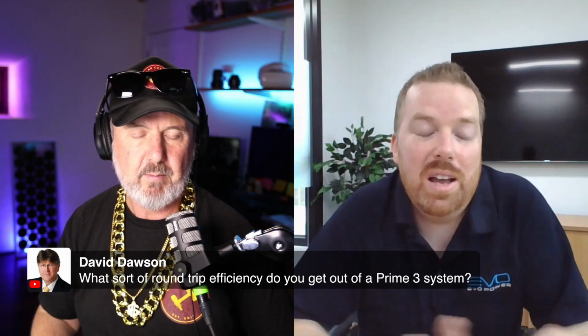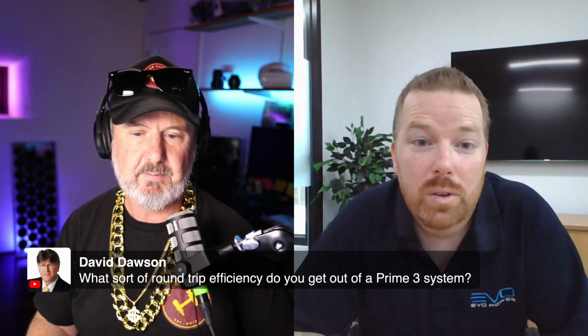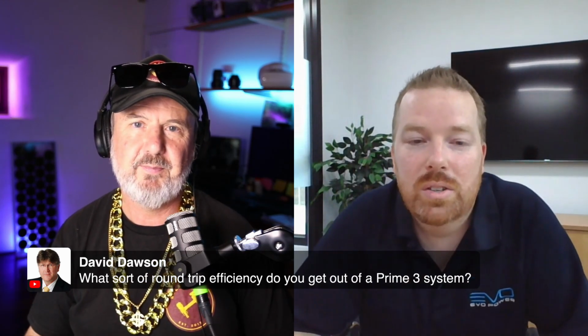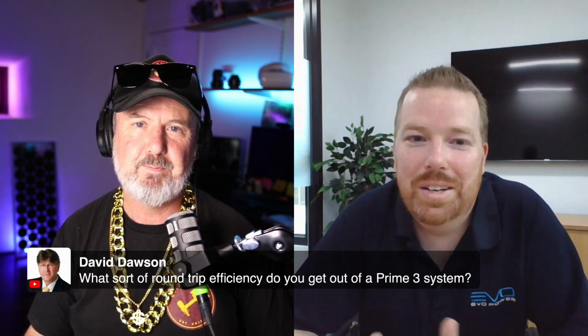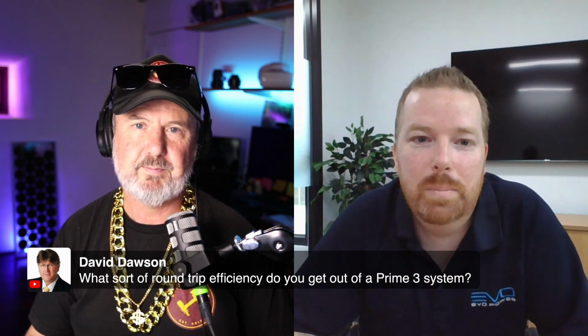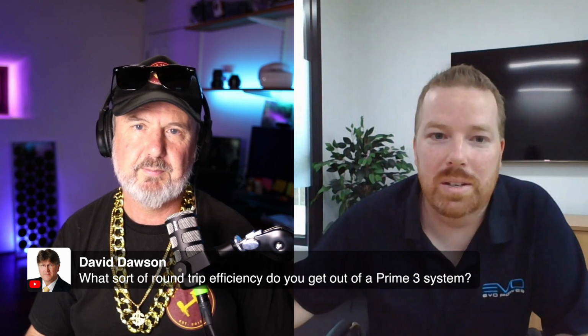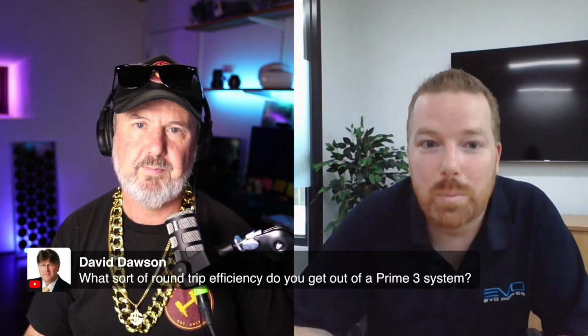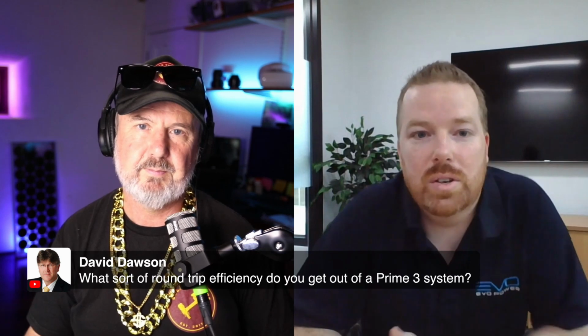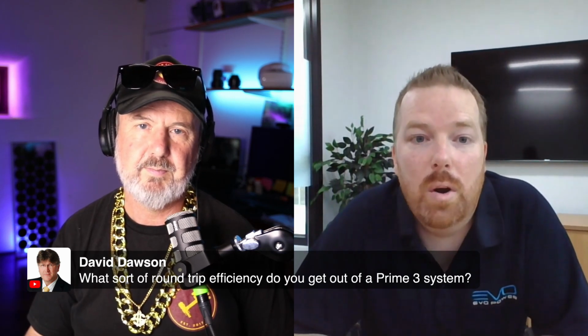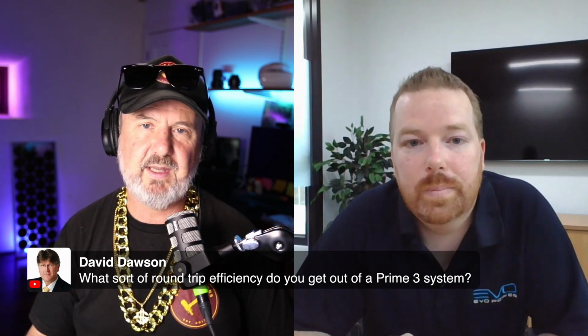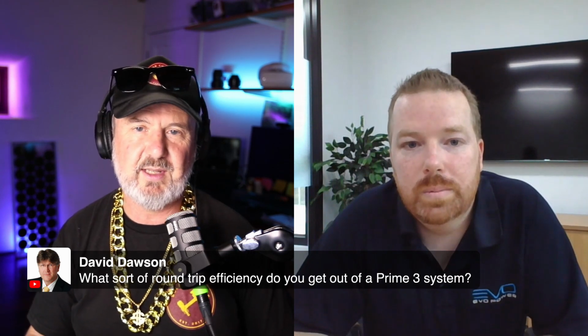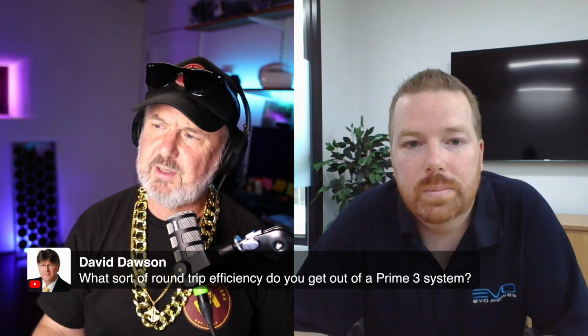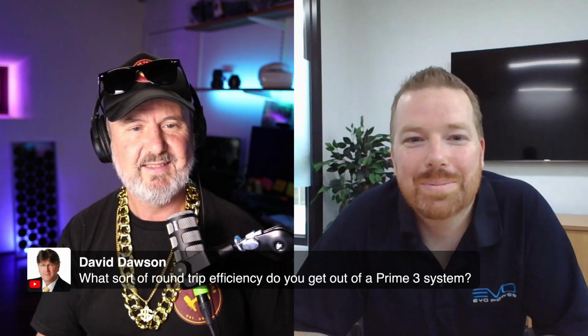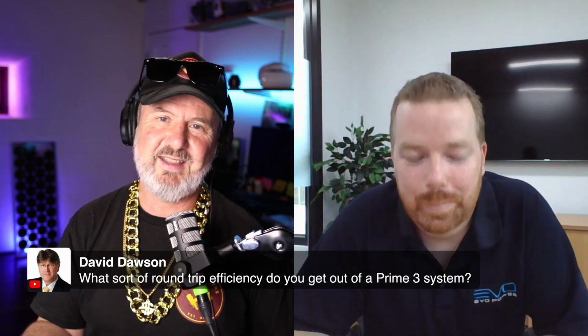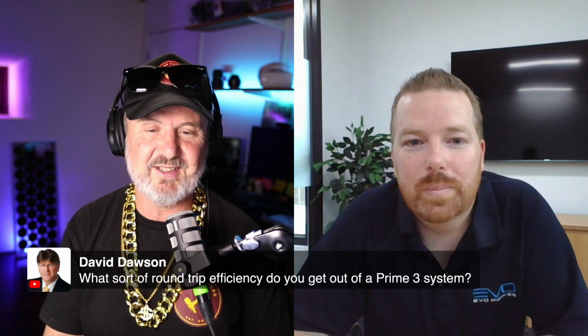It all depends on what the customer's loads are. From a design point of view, Glenn, I know you go through all this in your training courses, but it's really important to understand your customer's loads when sizing battery systems, because you may be oversizing it by 20%, and that's 20% more expensive, or vice versa. It's really important to get the design right. People always forget about the losses in a system - they think, I use 10 kilowatt hours a day, so I need a 10 kilowatt hour battery. Well, you'll never get that energy out of it because there's losses in the system.